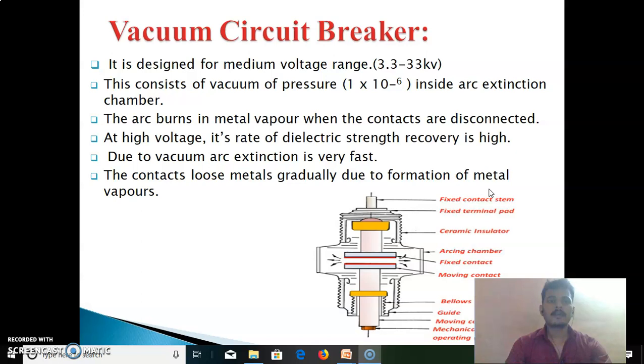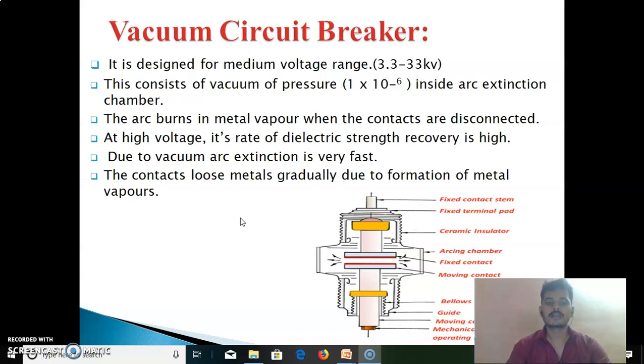There are some advantages of the vacuum circuit breaker. It has rapid recovery of very high dielectric strength on current interruption, so that only half a cycle or less of arcing occurs after proper contact separation. There is no emission of gases, hence it is pollution free. It has very high power frequency and impulse withstand voltage with small contact spacing, allowing ease of actuation and timing.